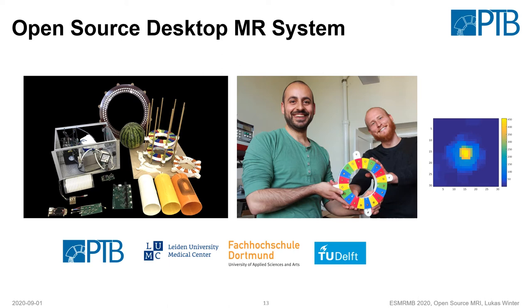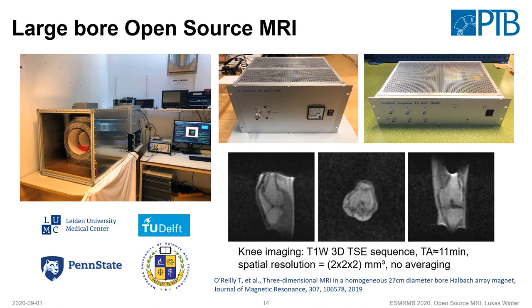In Berlin we built a magnet that is slightly bigger and a bit more colorful, as you can see on this photo of the students — it's also a collaborative effort. We have some first images of the prototype and are working on the second version to put it all together and document it. Here you can see a larger bore system for head or knee imaging, at Leiden University Medical Center in collaboration with partners from Delft, Penn State, and Makerere University. The prototype already showed some nice first knee images, and this system will also be rebuilt and certified for clinical imaging in children in Uganda.